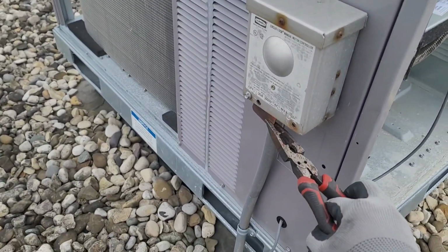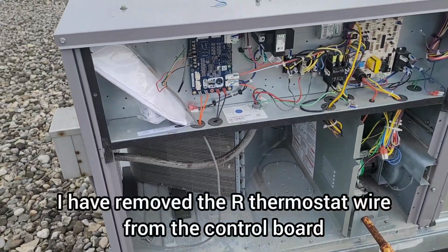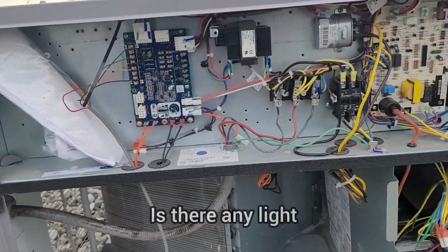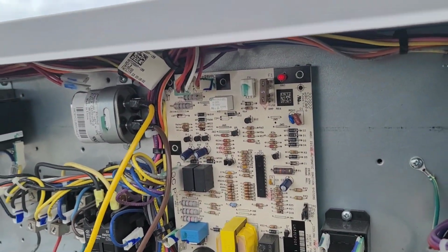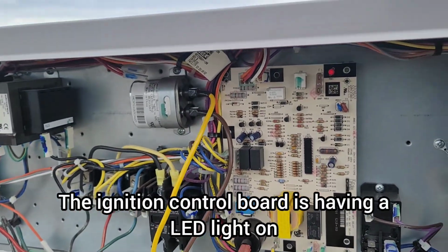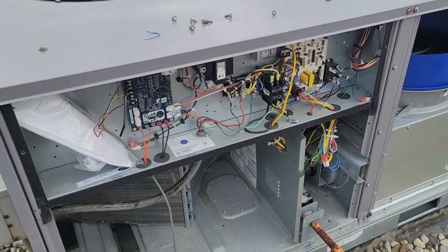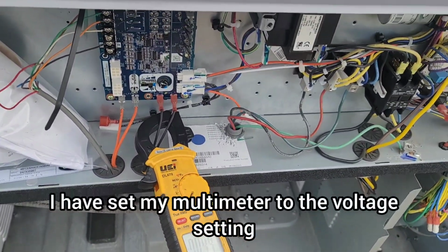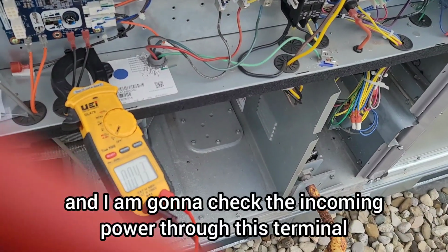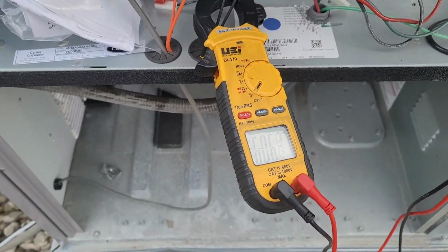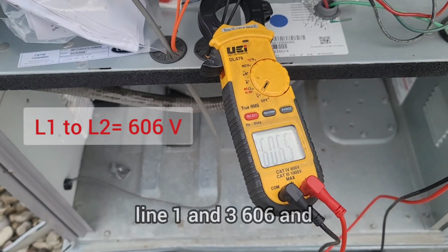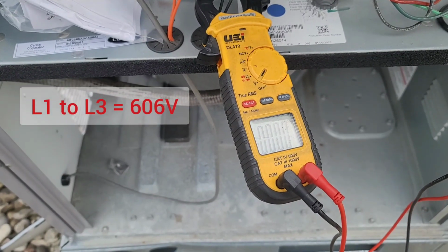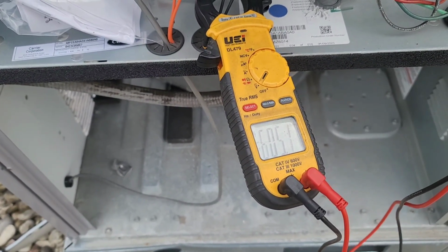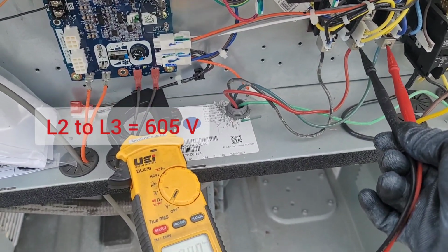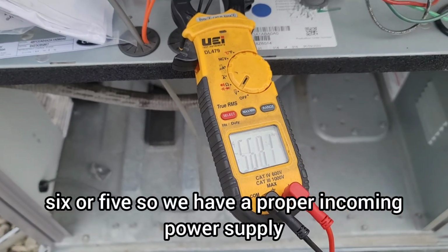Okay, let's turn on the power. I have removed the R thermostat wire from the control board. Is there any light? Yeah, just see. The ignition control board has an LED light on. I have set my multimeter to the voltage setting, and I'm gonna check the incoming power through this terminal. Line 1 to 2, 606; line 1 and 3, 606; and line 2 and 3, 605. So we have a proper incoming power supply.